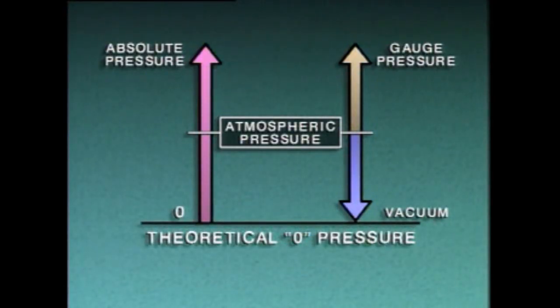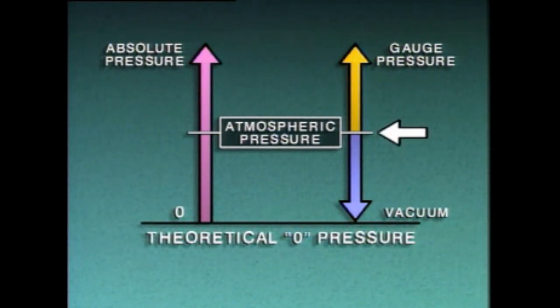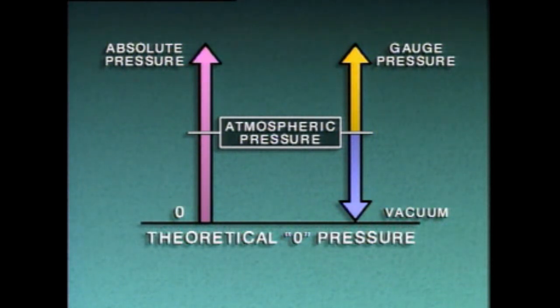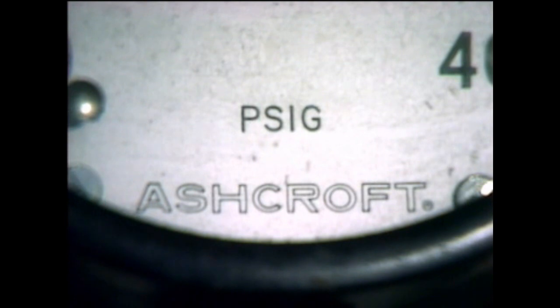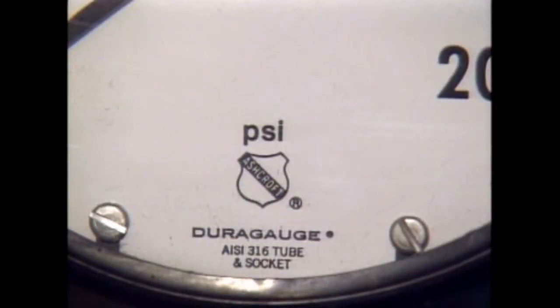Another type of pressure scale is the gauge pressure scale. The gauge scale starts at atmospheric pressure rather than at theoretical zero pressure. Since atmospheric pressure serves as the starting point, it's given a value of zero on the gauge scale. On an instrument that uses the gauge scale, pressure is indicated in pounds per square inch gauge, or PSIG. But sometimes gauge scale values are expressed simply as PSI.